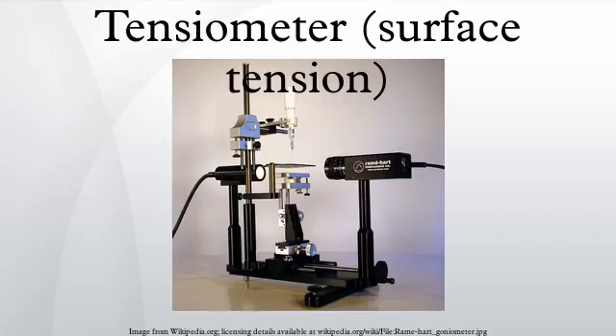Du Noüy-Padday method: This method uses a rod which is lowered into a test liquid. The rod is then pulled out of the liquid and the force required to pull the rod is precisely measured. This is a rather novel method which is accurate and repeatable. The Du Noüy-Padday rod pull tensiometer will take measurements quickly and unlike the ring and plate methods, will work with liquids with a wide range of viscosities.